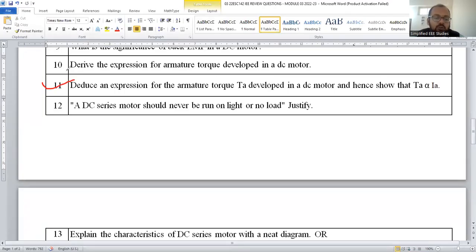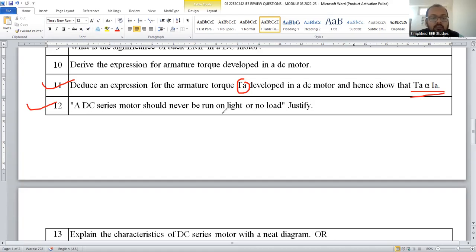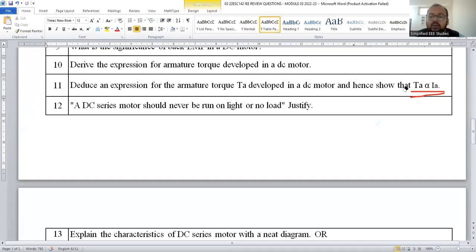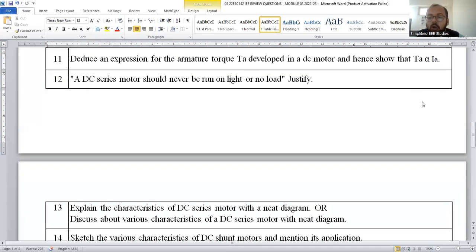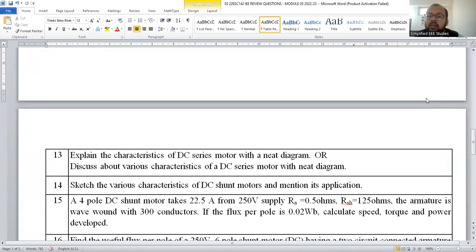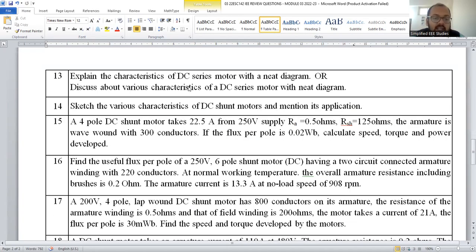Question 11 is a continuation: first derive the expression for Ta, then prove that Ta is directly proportional to armature current. Another important question is: why should a DC series motor never run at light load or no load? Because if you operate the DC series motor at no load, the motor reaches a dangerous speed — you can explain this with the help of motor characteristics. Whenever you want to start a DC series motor, you have to apply a certain load first; otherwise the motor goes to dangerous speed and the winding burns, damaging the motor.